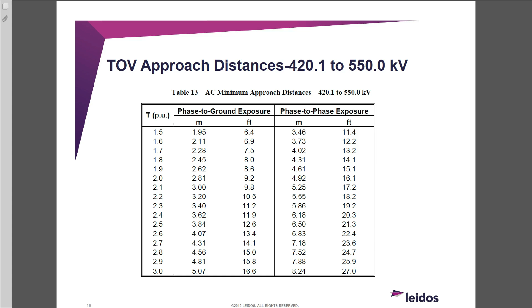So one more thing to point out: if you didn't do any of this analysis, you have to use the default, which is 16 feet. That's still a lot. That's why 2.4 was the number a lot of our clients were aiming for at 500 kV, because that's pretty close to their safety distances.